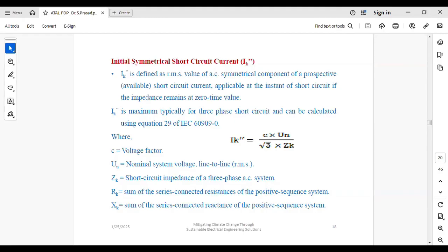We calculate the initial symmetrical short circuiting current and its value. Suppose you have to consider a circuit breaker at a particular feeder, and the short circuiting current in that feeder is more than the breaker rating, then that breaker capacity is not acceptable at all. So you have to go for a higher rating. That's why we conduct short circuit analysis, to know how much maximum short circuiting current will flow through a feeder line in a PV system.